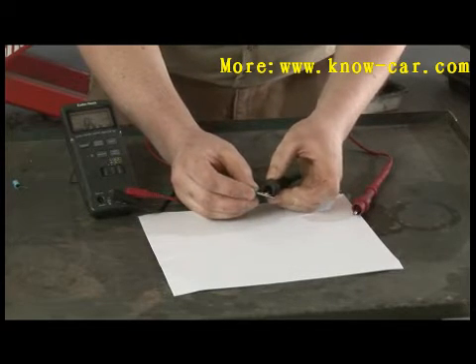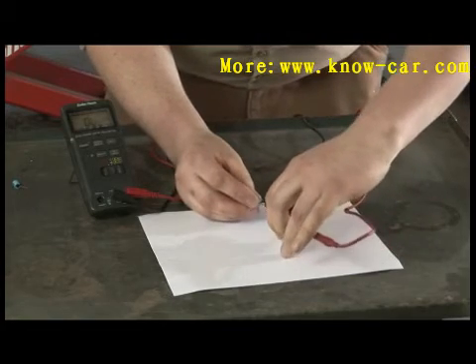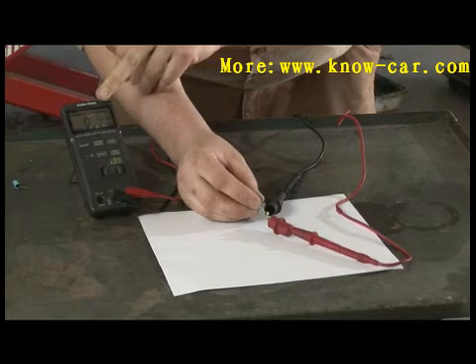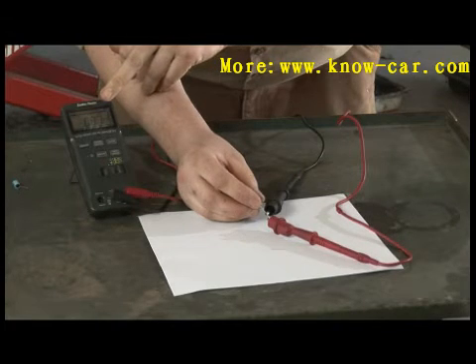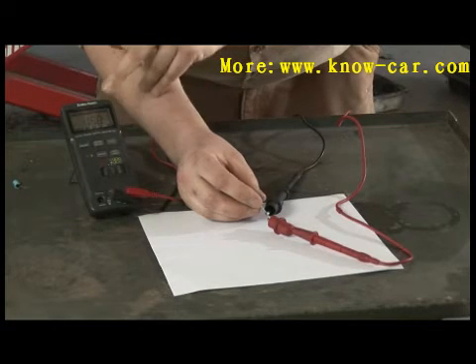Once it's discharged, you hook up your negative lead to the negative side of the capacitor, and your positive lead to the positive side. What you will see is that the resistance will increase as the capacitor slowly takes a charge from the test voltage coming from the meter.